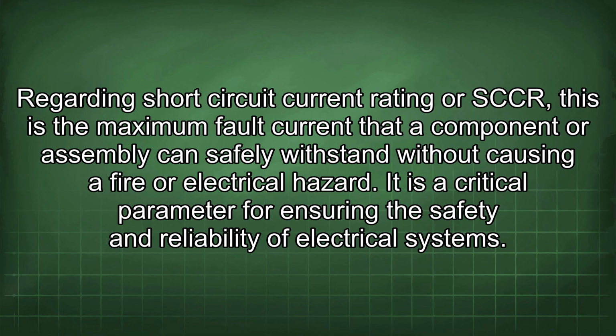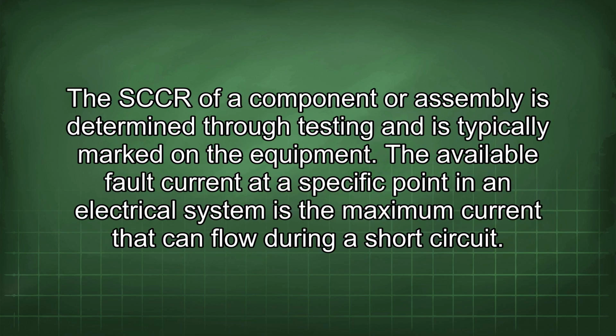Regarding short circuit current rating or SCCR, this is the maximum fault current that a component or assembly can safely withstand without causing a fire or electrical hazard. It is a critical parameter for ensuring the safety and reliability of electrical systems. The SCCR of a component or assembly is determined through testing and is typically marked on the equipment.